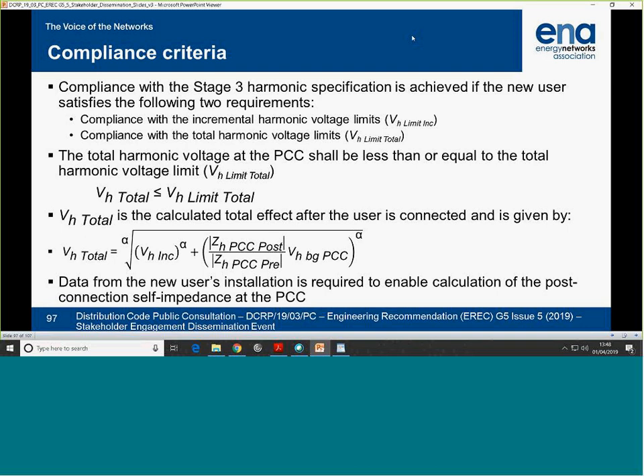In order for the utility to check compliance, the user needs to provide the VH total, which is the total effect of the customer. It's not the same as the total limit, which is what we produce. This is what the customer produces, choosing the equipment and design. The total effect of the customer is the incremental effect. It is produced through emission and also magnification of the background.